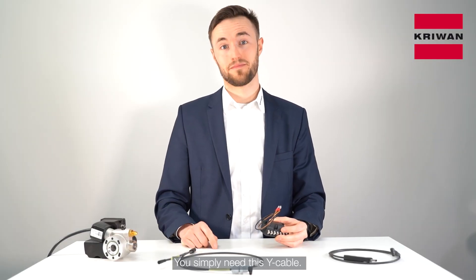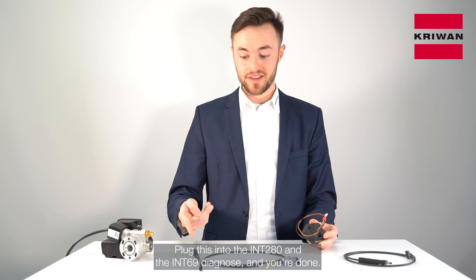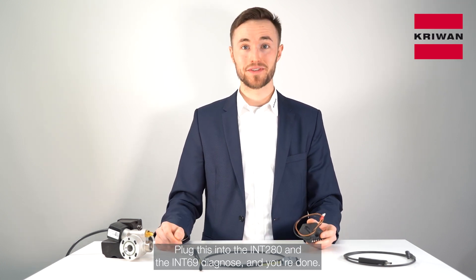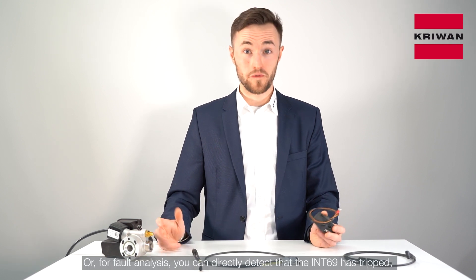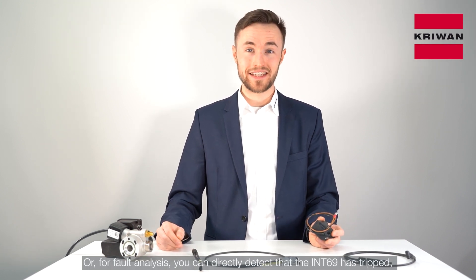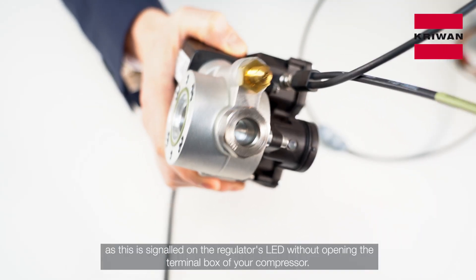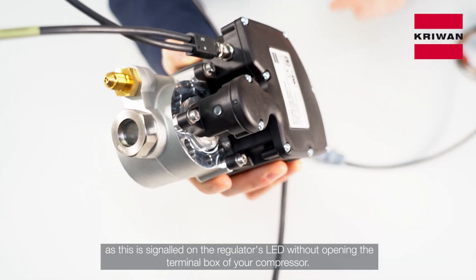You simply need this Y cable — plug this into the INT280 and the INT69 Diagnose and you're done. For fault analysis, you can directly detect that the INT69 has tripped as this is signaled on the regulator's LED without opening the terminal box of your compressor.